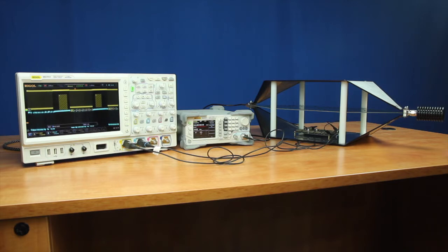Based on the geometry of the cell, we can approximate that a plus 20 dBm signal generates a maximum field strength of about 22.3 volts per meter. That's between the septum and the bottom wall. Susceptibility to a particular field strength can then be tested based on frequency, field strength, modulation, and other functions.